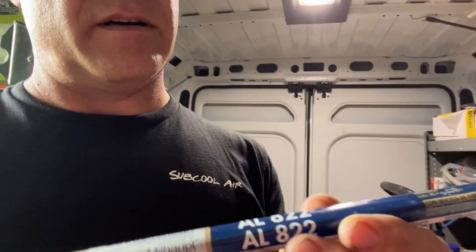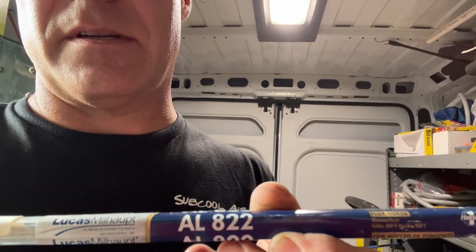Hey guys, thanks for tuning in. I just want to give you a quick video. I was at a job yesterday and had to repair a leak on an aluminum coil — it's a residential call. I use this AL822; you can see I've used these rods before and had good success with them. I didn't get a chance to video it, but I have a small clip of the actual leak — it was on a distributor tube right in the front, very fortunate. I got that patched up, and I'm back today to put a UV bulb back in that coil. This customer I've taken care of over the years and she's got a bunch of cats, so I'm trying to keep these coils clean. We're going to follow up — I'll show you how the patch looks.